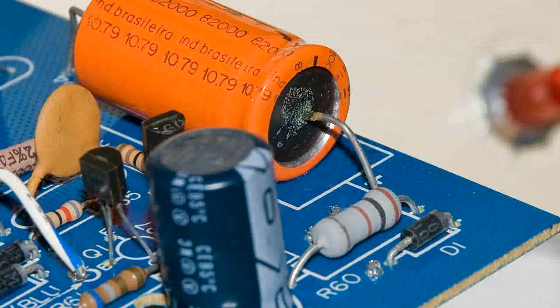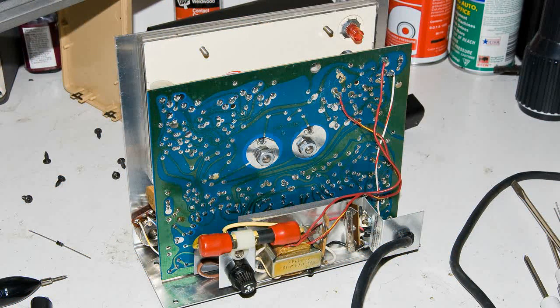So I removed all of that and put in a new 100 ohm resistor. And here I am testing it out a little bit to make sure that the meter will function. And that was, at least right now, the major problem. The meter now seemed to function on all scales.